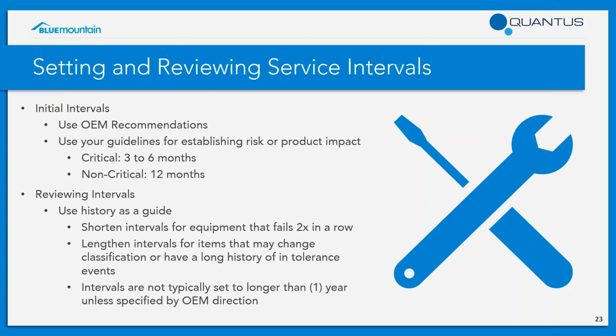Getting into setting and reviewing service intervals, again, the best place to initially start is your OEM recommendation. Manufacturers typically know their equipment best and what type of drift to expect over time. So in most cases, we see that manufacturers are stating at minimum 12 months, you should be calibrating or performing preventative maintenance on your service. But you tend to want to look a little bit deeper at the process requirement and your risk assessment. So what we typically see and recommend in the industry for critical equipment, you should be testing that every 3 to 6 months. And then non-critical equipment can be pushed out to every 12 months.